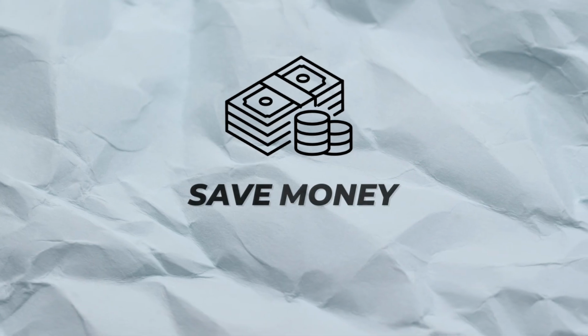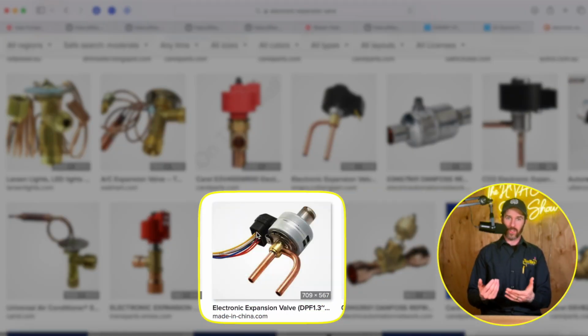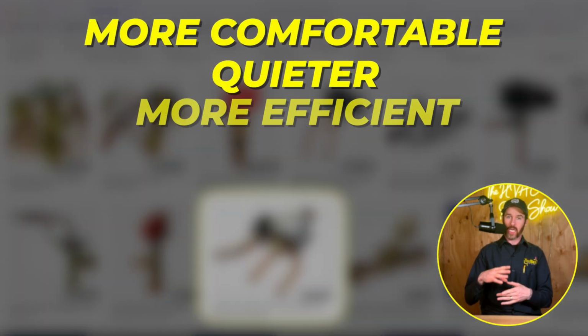The benefit is that your compressor and your indoor unit are now working in unison, and that's part of how it's maximizing efficiency. So number one, you're going to save money, and that's how it becomes a more efficient system. But number two, it's actually better at cooling or heating, in that it's more accurate when it first kicks on, so it's maximizing heat removal or heat transfer, which is what air conditioning is. It's just heat transfer through the refrigerant. In the summer, we take heat from inside the home and send it outside through the refrigerant, and in the winter we pull heat from outside and put it into the refrigerant and send it inside. So an electronic expansion valve is just an added comfort feature that makes the system more comfortable, quieter, more efficient, and better at operating. This is one of the biggest selling points on those high-end systems, that you do get a system that has an electronic expansion valve.